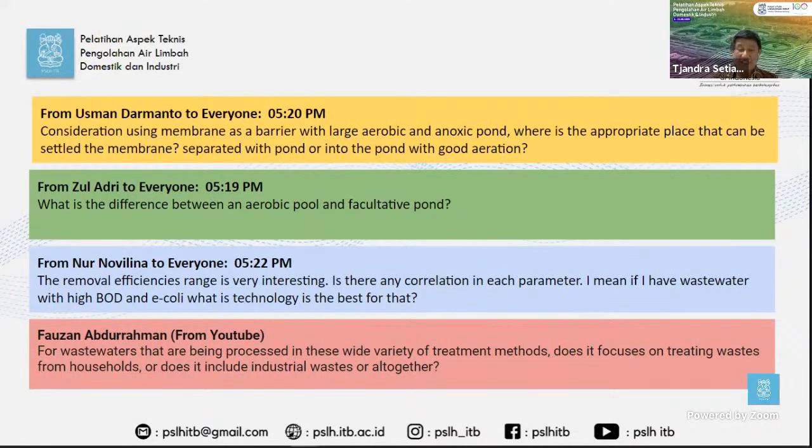Yes, thank you. Yes, there is, because these biological treatment processes I showed you can also be used for treating industrial wastewater, provided the industrial wastewater has biodegradable organic matter. So depending on the processing of the industry, if it is a dairy industry, a beverage industry, a slaughterhouse, a tannery, and so on, that produces effluents with lots of organic matter, you can use these biological treatment systems. If you have an industry that does not produce an effluent with organic matter, but with metals, with non-biodegradable components and so on, the biological treatment will help you very little. And okay, you can also use a combination.